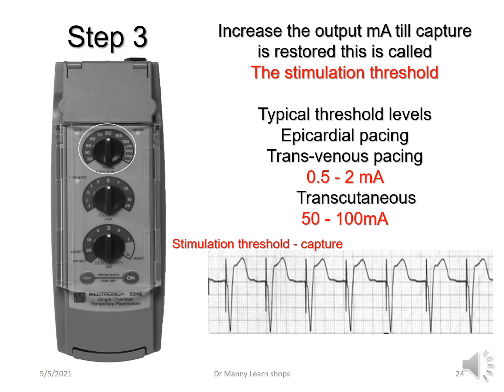Typically, the stimulation threshold in epicardial and transvenous pacing is around 0.5 to 2 milliamps. In transcutaneous pacing, because it's outside the body and the skin increases trans-thoracic resistance — stopping electricity from reaching the heart — you need higher outputs. Typically in transcutaneous pacing, you need 50 to 100 milliamps to achieve capture or the stimulation threshold.